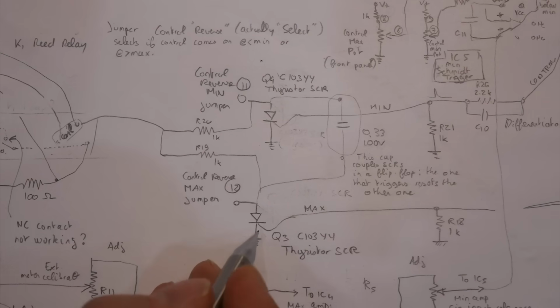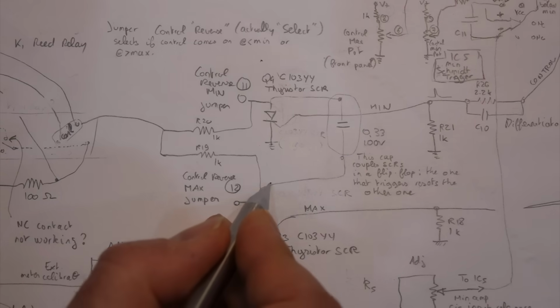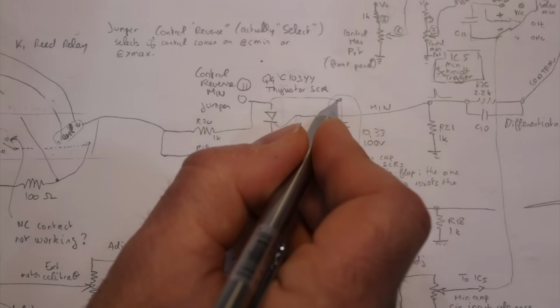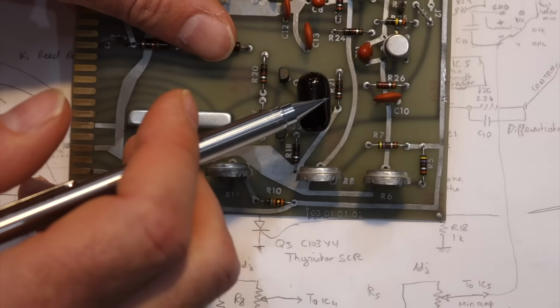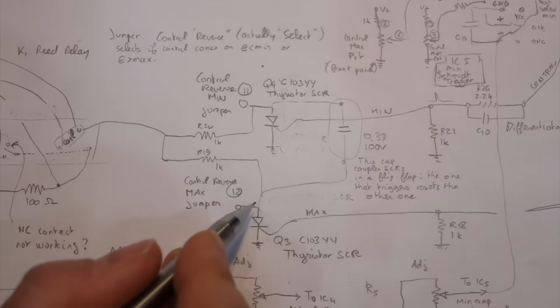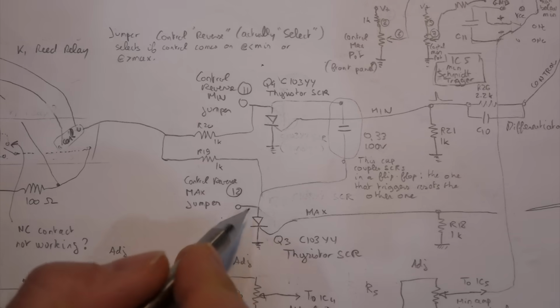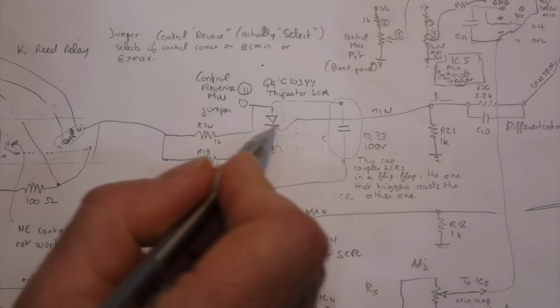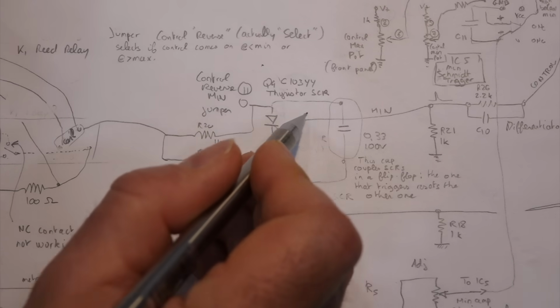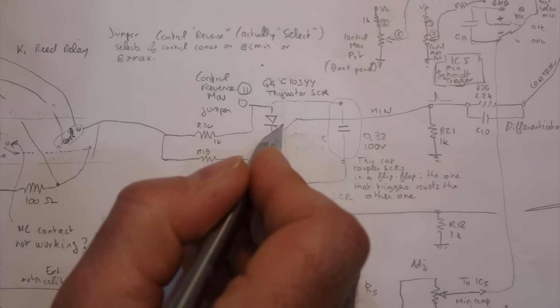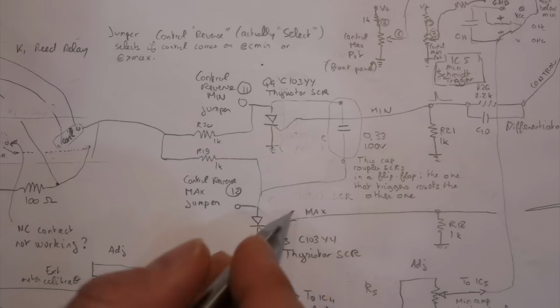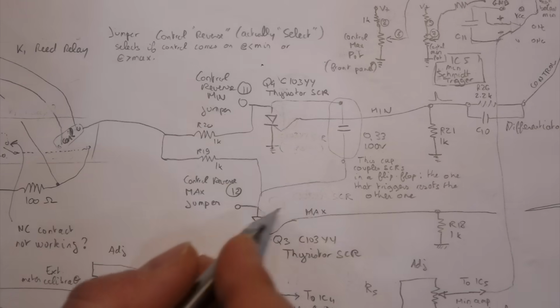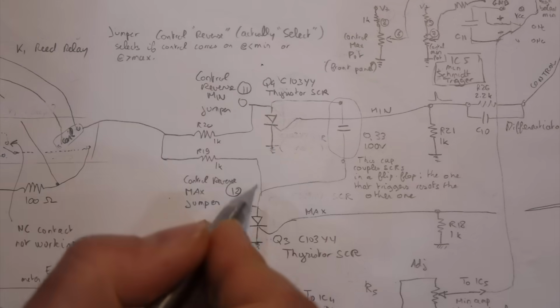So when you hit the maximum, now this guy triggers, and it's coupled to the other one via the capacitor here, which is that big giant capacitor over here. I was wondering what it was doing. And basically, since this one will become conductive, there will be a pulse traveling through here, and it will turn this one off. It'll put this one at zero. And this one won't recover because it's not triggered anymore, and this one will continue. And vice versa, when this one is triggered at the minimum, it turns off this one. So it flip-flops the control within the dead band.